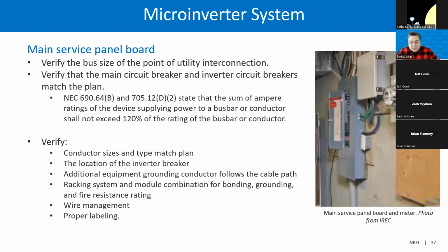So the last major item we will consider relative to the microinverter system is the main service board and meter. The inspector must verify that the bus size of the point of utility interconnection, the main circuit breaker, and the inverter circuit breakers must match the plan. The sum of ampere ratings of devices supplying power to a bus bar or conductor shall not exceed 120% of the rating of the bus bar or conductor, similar to what we have described in the previous section.